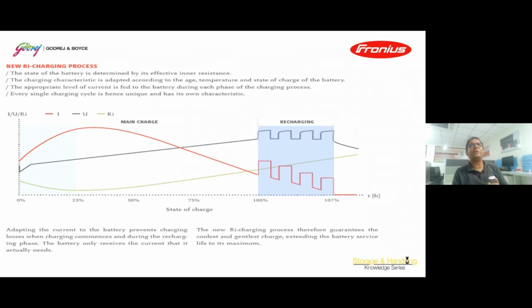But with this predefined charging process, there are some disadvantages. When the battery gets discharged to 80% on the MHE vehicle, normal practice as recommended by battery manufacturers is that the battery should sit idle for 1 or 2 hours to cool down. The reason is that when the battery discharges drastically, the inner resistance of the battery increases, and because of the resistance, the temperature of the battery also increases.